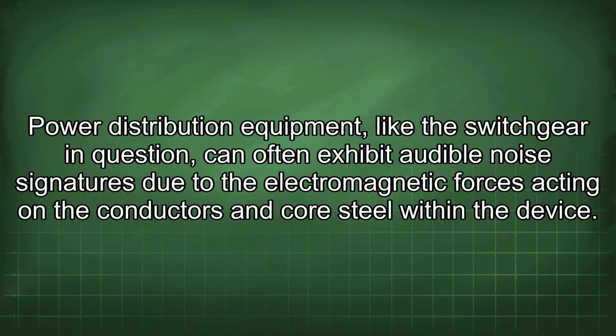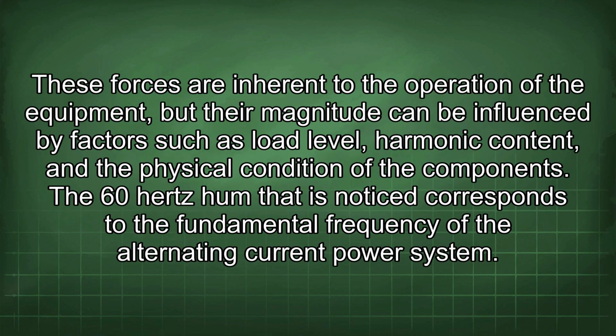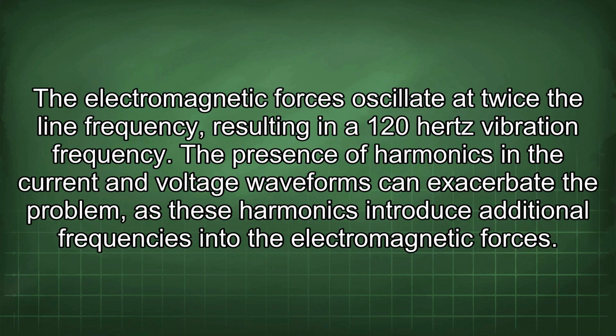Power distribution equipment, like the switchgear in question, can often exhibit audible noise signatures due to the electromagnetic forces acting on the conductors and core steel within the device. These forces are inherent to the operation of the equipment, but their magnitude can be influenced by factors such as load level, harmonic content, and the physical condition of the components. The 60 Hz hum that is noticed corresponds to the fundamental frequency of the alternating current power system. The electromagnetic forces oscillate at twice the line frequency, resulting in a 120 Hz vibration frequency.